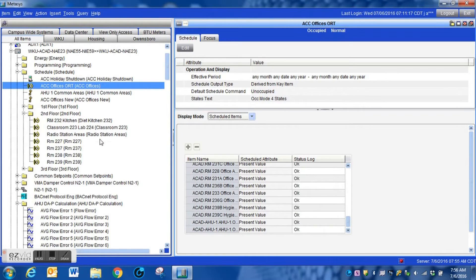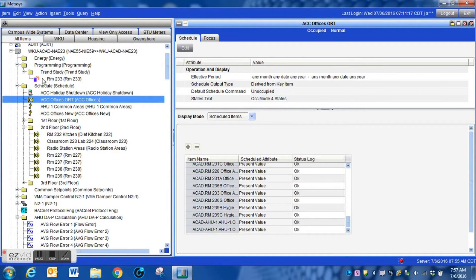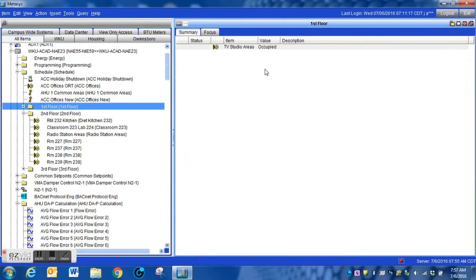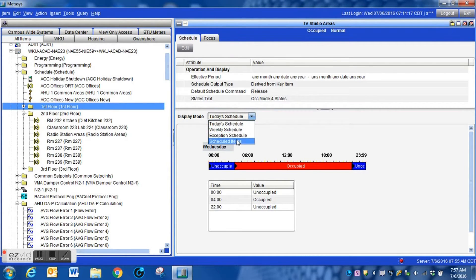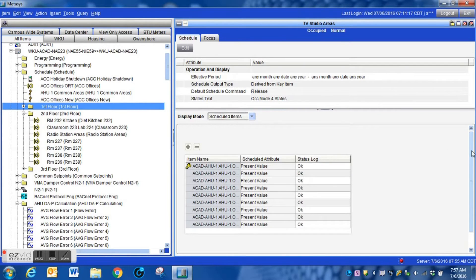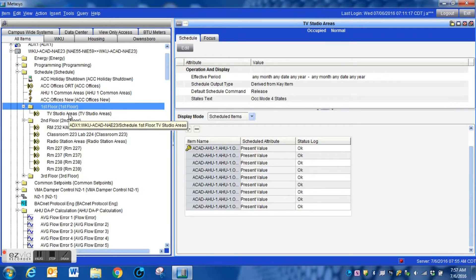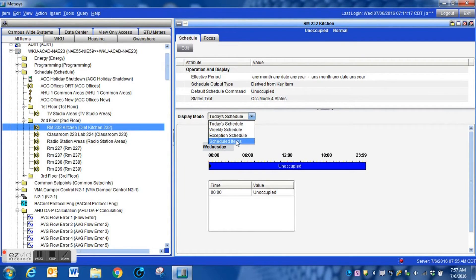Looking through your schedules — if you find any VAVs or anything within the schedule that shows it is busy binding, pending, or anything like that, verify that the controller is still within the system. If it is not, go into your scheduled items and remove it from that schedule. Be very meticulous in doing this — spend the time and go through every single logic block within your system.